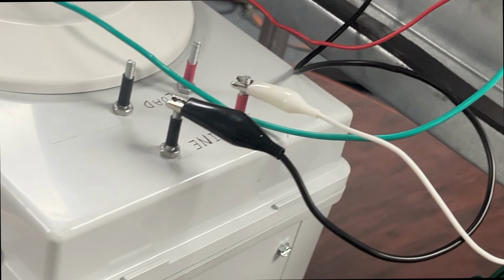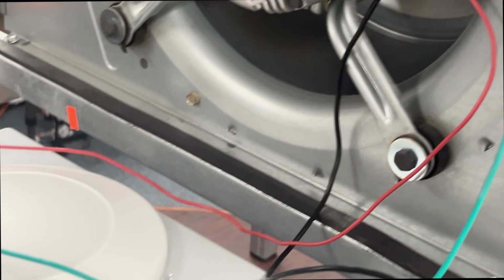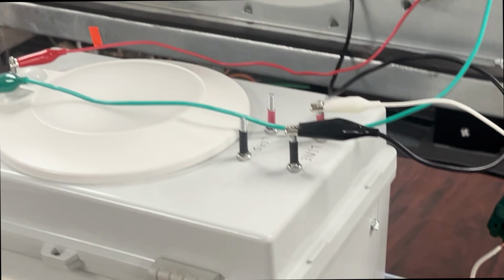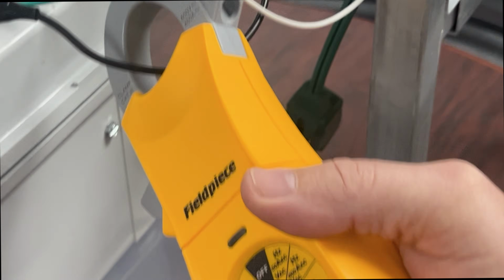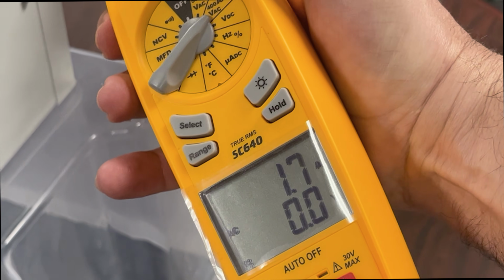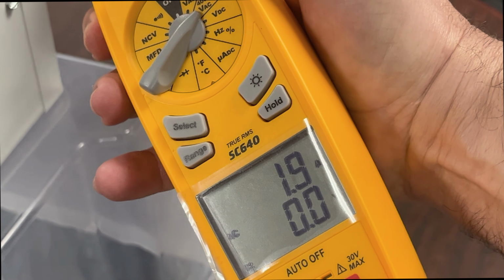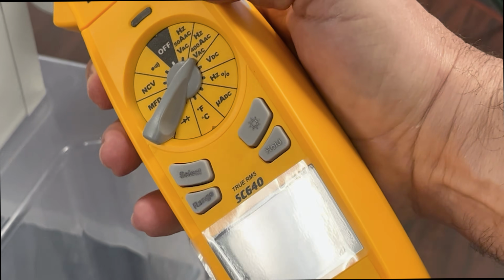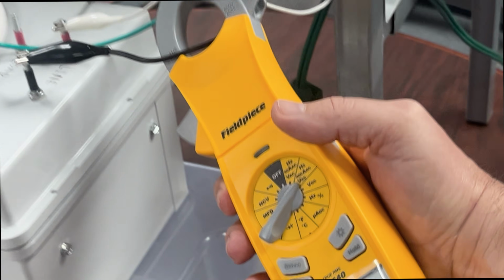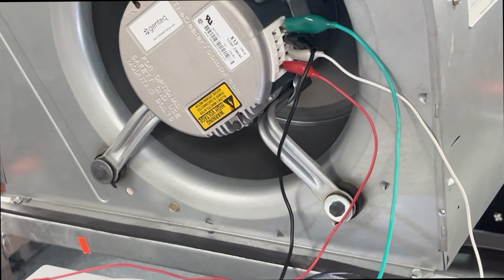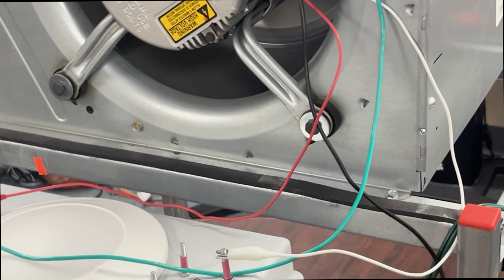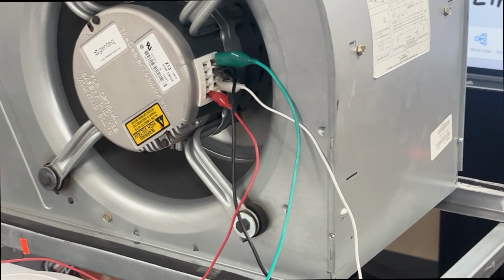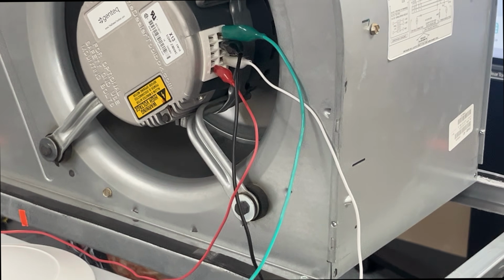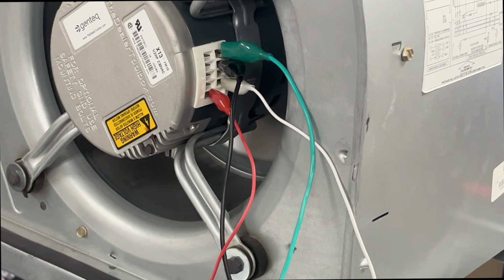Okay, our line voltage. And I want to show you what that amp draw is now that we have 230 volts there. Go ahead and clamp it. And you see we're not getting 2.9, we're getting 1.8, 1.9 amps. That's a big difference here. All right, we're gonna go ahead and turn the power off. Okay, we're gonna show you one more perspective here.